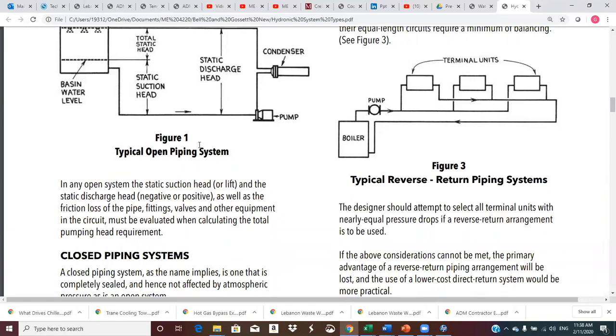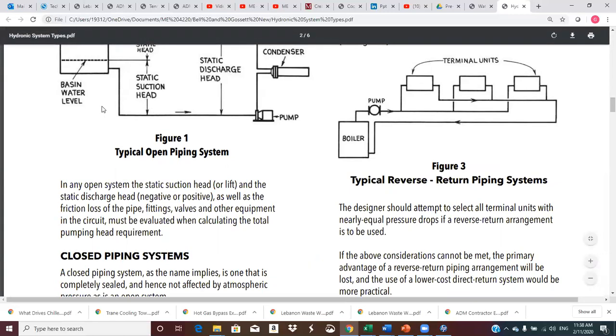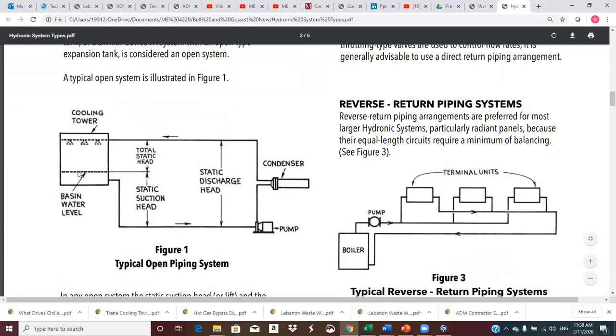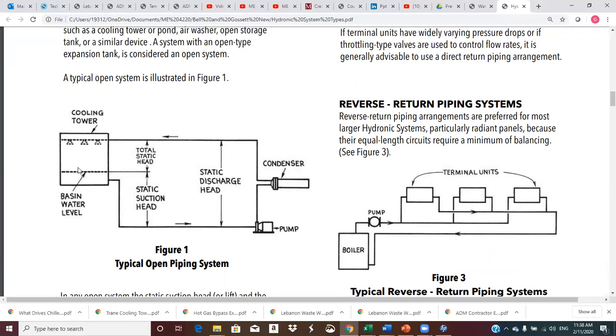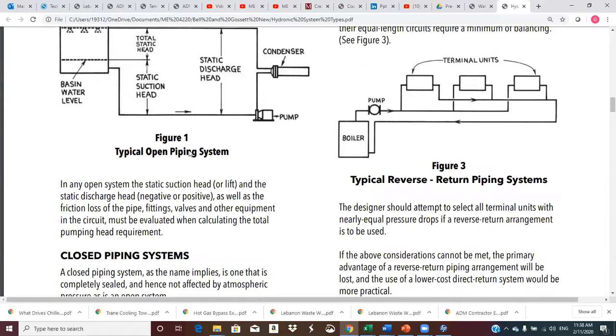Okay, let's see what they say here. And this head can actually be negative. In this case, not necessarily in a cooling tower, but we could have a tank up here that we're pulling out of, and then this could go to a tank that's down here someplace, in which case that static difference would be helping the pump instead of making the pump supply it. So the static head can be plus, minus, or zero on this.